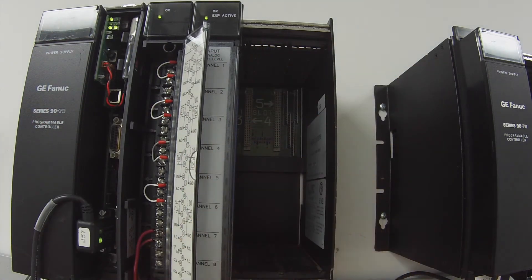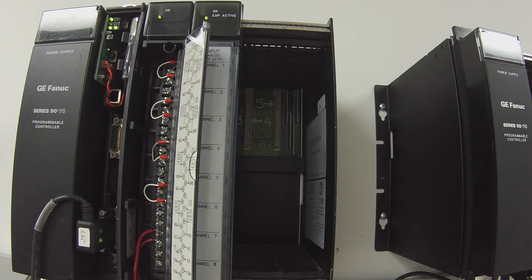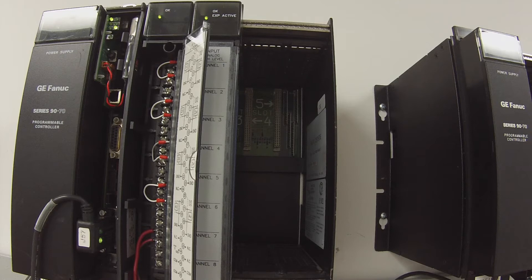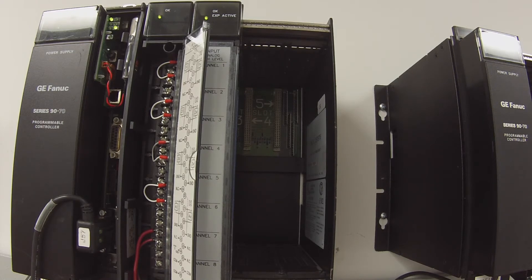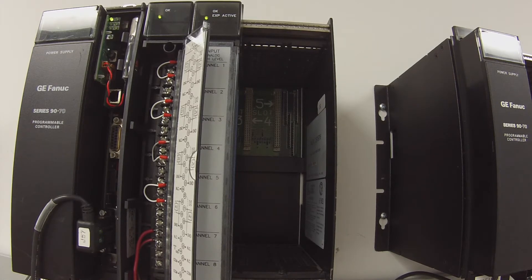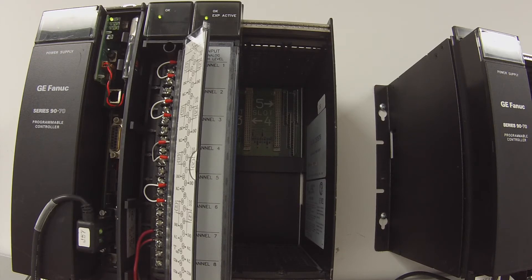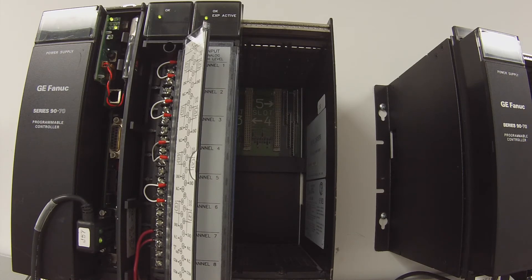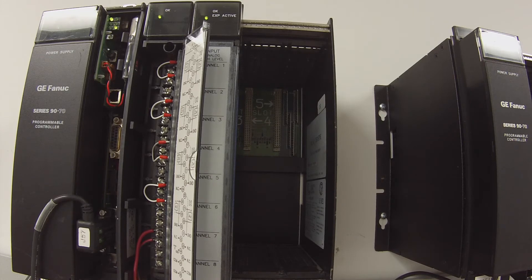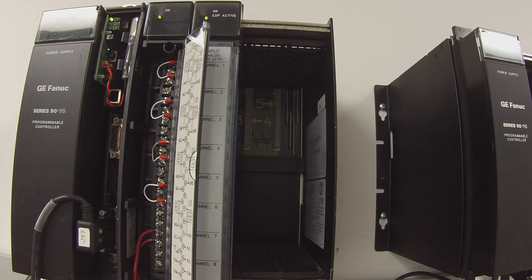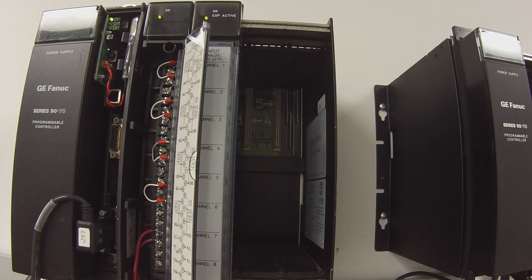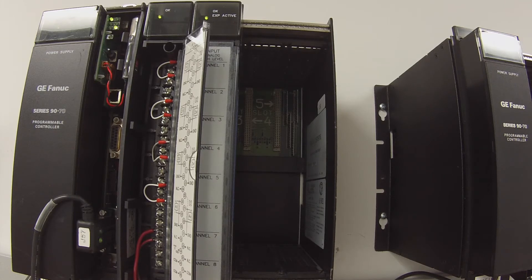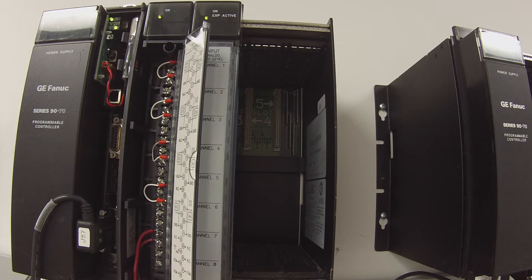Now we're going to test milliamp. I'm going to stop my processor, go into the configuration of the ALG320, the four channels, and switch it to 4 to 20 milliamp and it'll change my output and the output location. Once I've configured that, you need to go back in and clear controller and IO fault table because you've made a change.